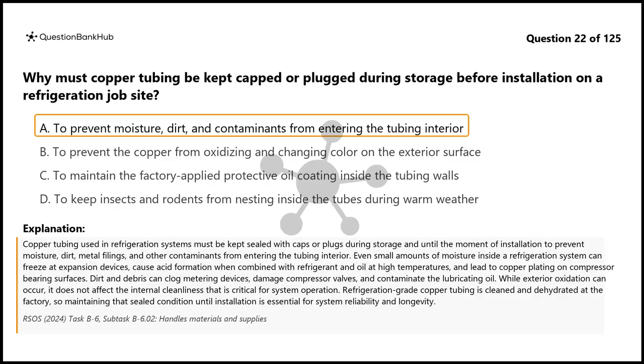Copper tubing used in refrigeration systems must be kept sealed with caps or plugs during storage and until the moment of installation to prevent moisture, dirt, metal filings, and other contaminants from entering the tubing interior. Even small amounts of moisture inside a refrigeration system can freeze at expansion devices, cause acid formation when combined with refrigerant and oil at high temperatures, and lead to copper plating on compressor-bearing surfaces. Dirt and debris can clog metering devices, damage compressor valves, and contaminate the lubricating oil.